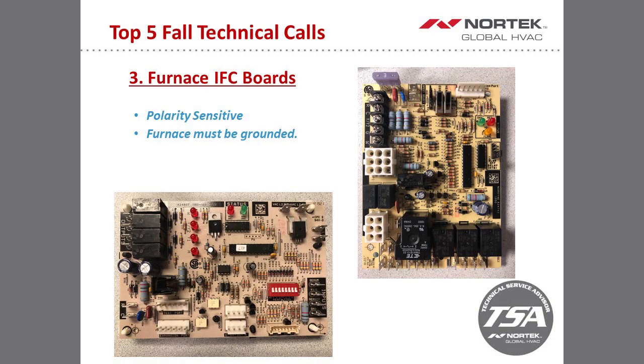And then also, just a quick reminder is that the blower speeds are not factory set. So what I have here is a variable speed board. You see the red box there on the variable speed board, that's where your dip switches are set. Again, that can be found in the install instructions. And then I have a single stage board there where you have selector switches to then set your blower speeds for a PSC motor setup. The dip switches and those blower speeds will have to be set in the field, again, based on your duct static pressure. But again, all that stuff can be found in the install instructions, which will come with the furnace.